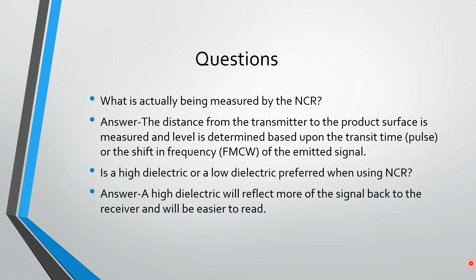This one, the 3Ds of radar level measurement. Give you a second just to think about that while I take a sip of water. And if you remember the 3Ds, it was dielectric, distance, and disturbances. We want to make sure the dielectric is high enough to give us proper reflection. We want to make sure the distance that we're trying to measure is compatible with the device that we're using. And we want to know what disturbances there are that will cause unwanted reflections.